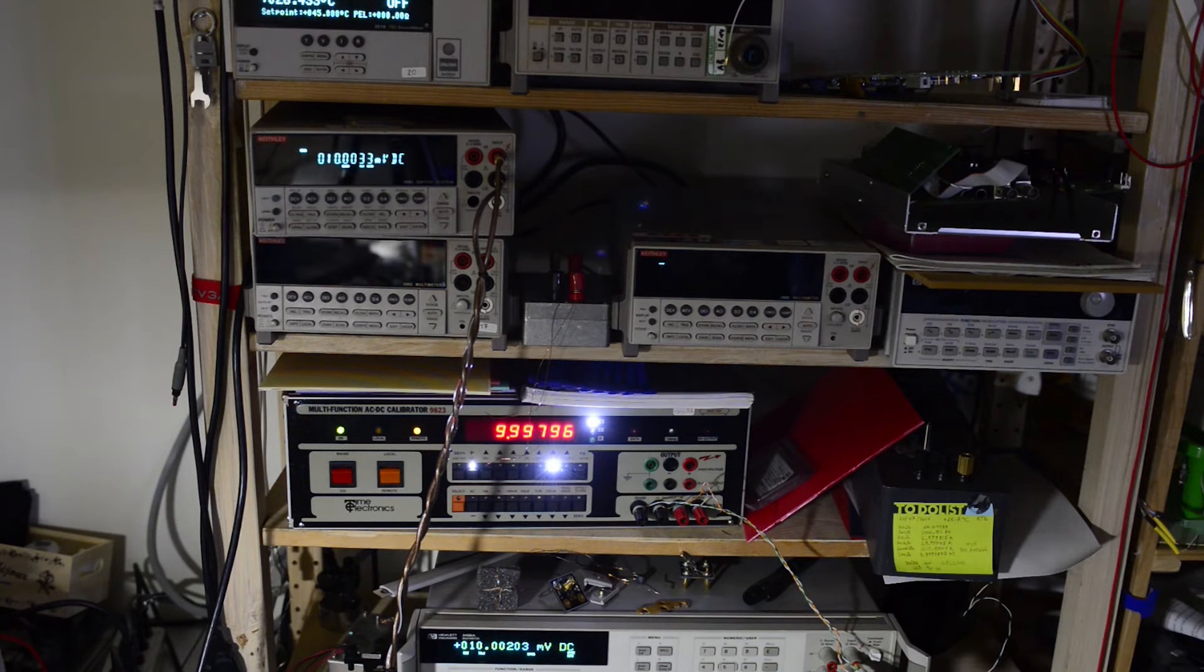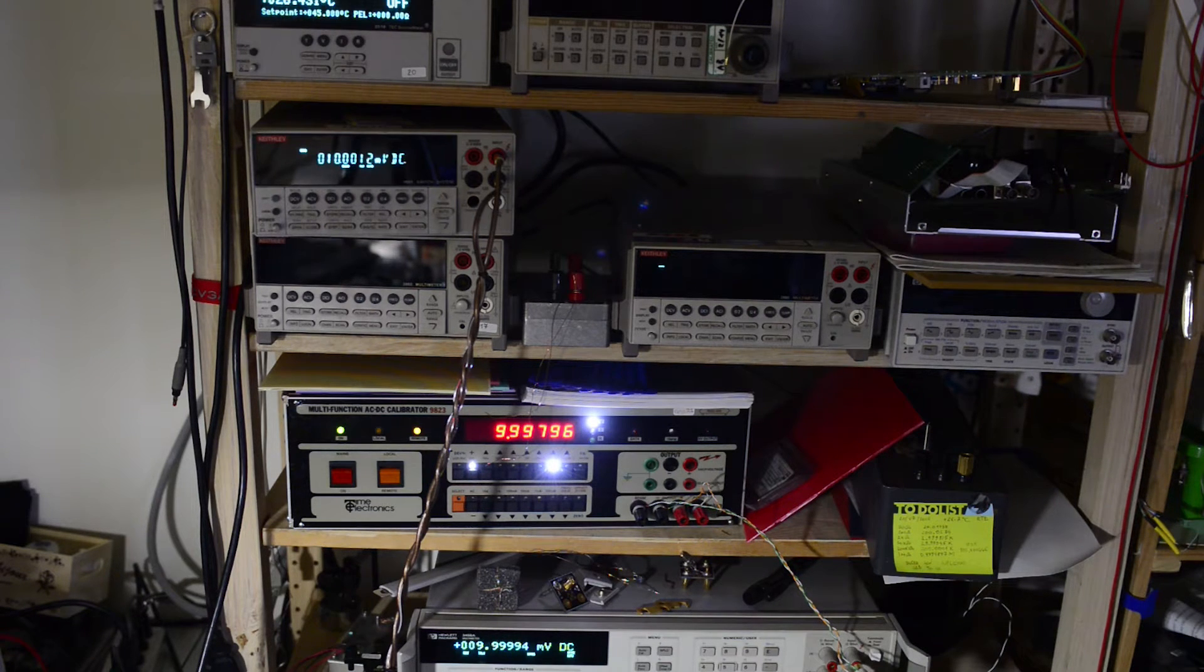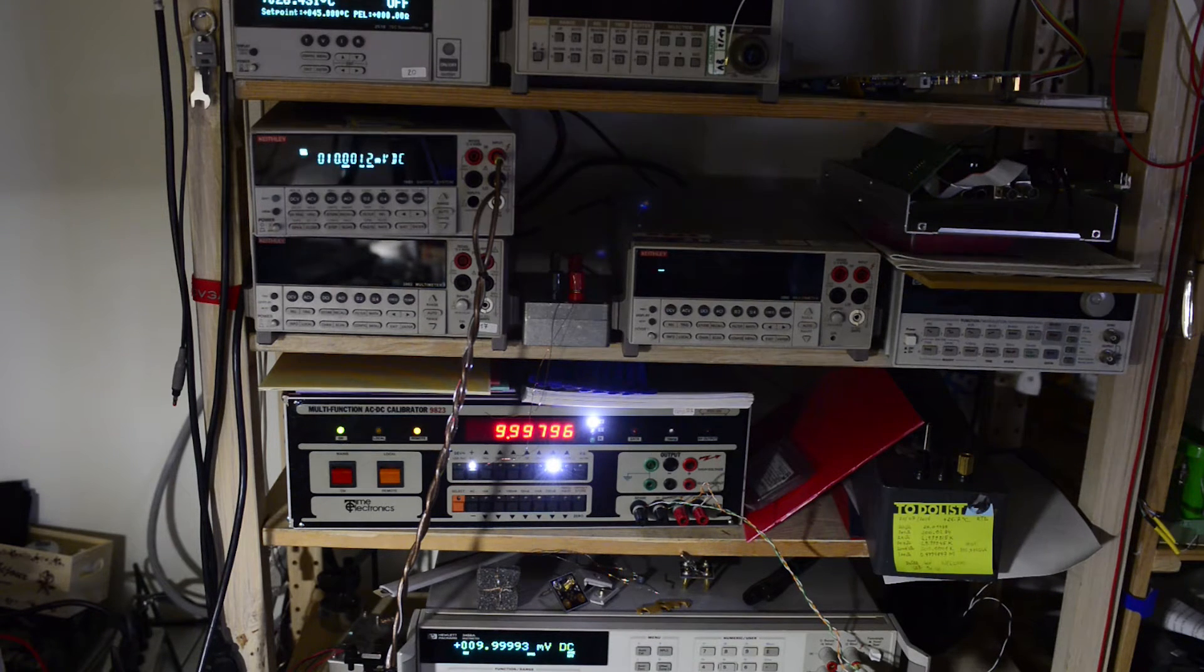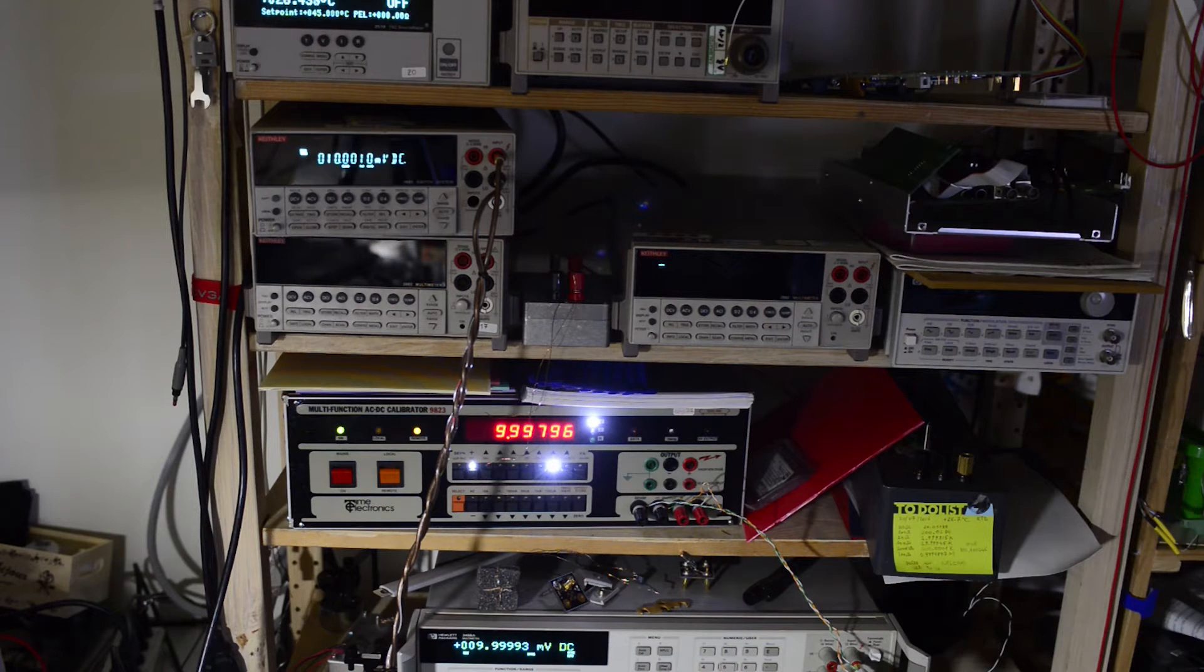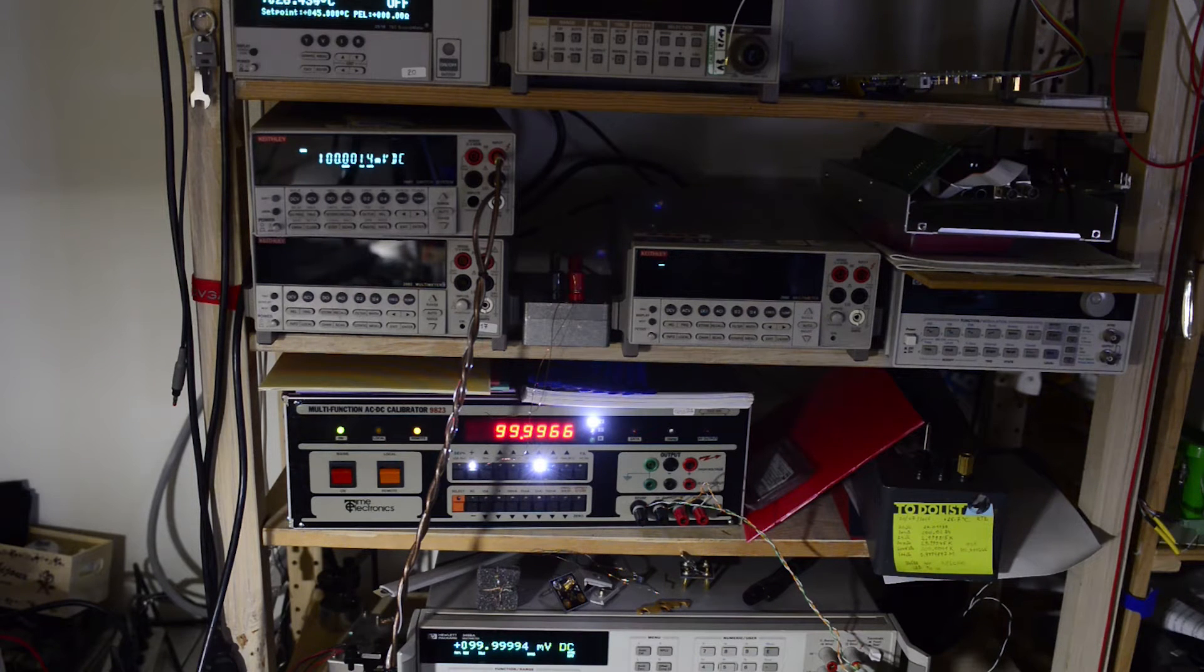Also you can notice I implemented automatic correction for the calibrator output based on 3458A reference measurement. This is very simple piece of code which will have the DMM take two readings first and then apply the offset to calibrator output to get the perfect setting. It's not required for calibration purposes because model 2000 DMM can accept calibration values within 10% range.